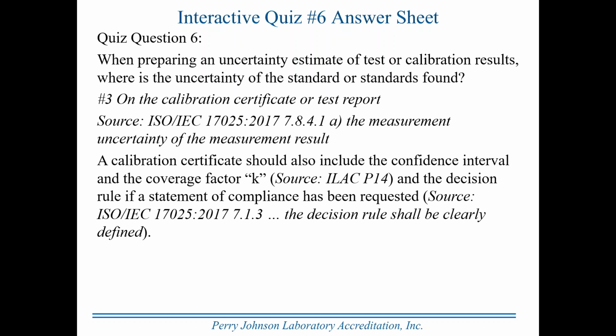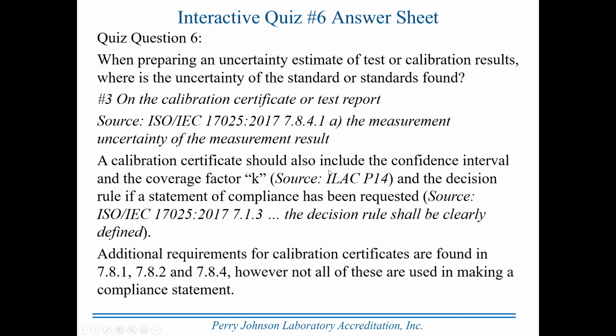The decision rule shall be clearly defined on the calibration certificate. Additional requirements for calibration certificates are found in sections 7.8.1, 7.8.2, and 7.8.4. However, not all of these are used in making a compliance statement, so I didn't reproduce them on this slide. Now you'll notice that 7.8.3 is not included there. Very good reason for that.